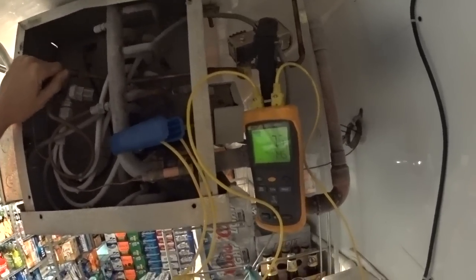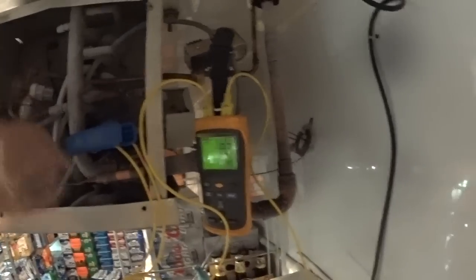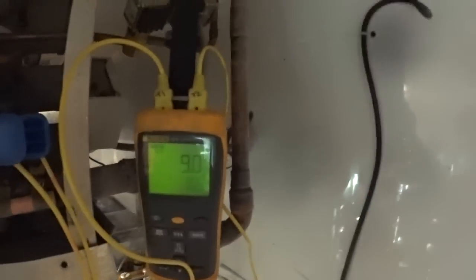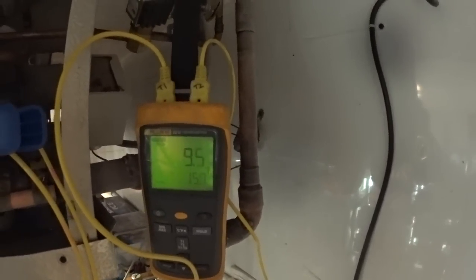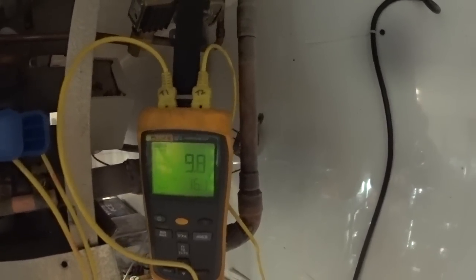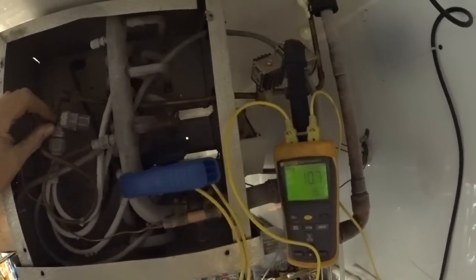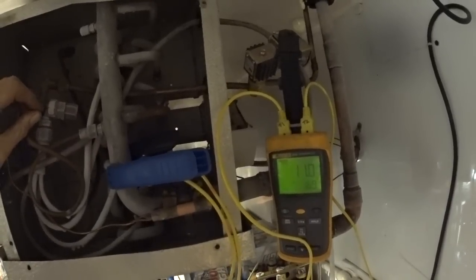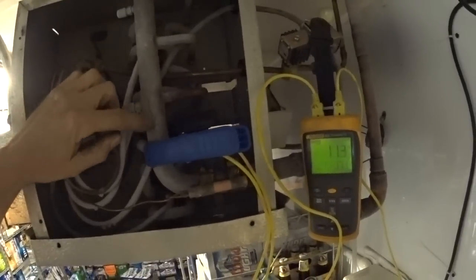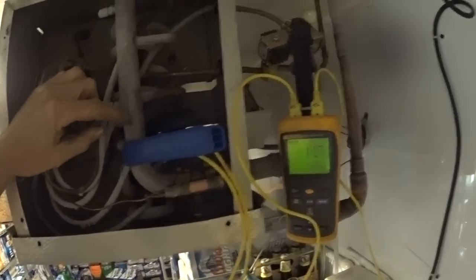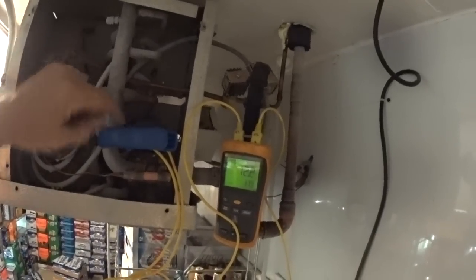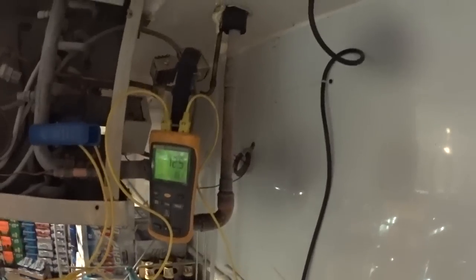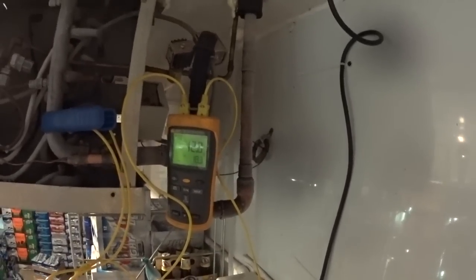You know, I just spent a lot of money on the compressor. If I see it rising, what's happening is that the expansion valve is closed off now, and it's allowing less refrigerant going through, so it's allowing the temperature difference between the inlet and the outlet to rise. And I'm up, this is where I'd like to keep it, around here, 12, 13.